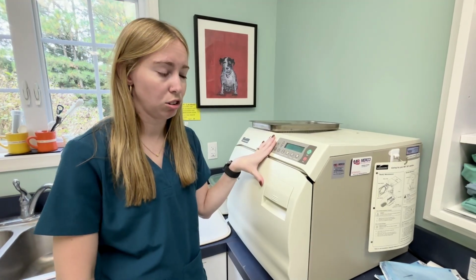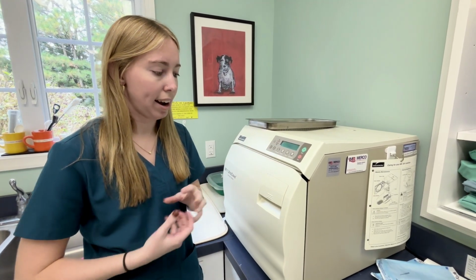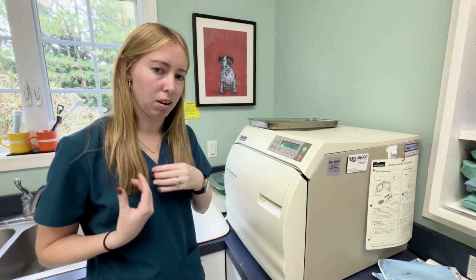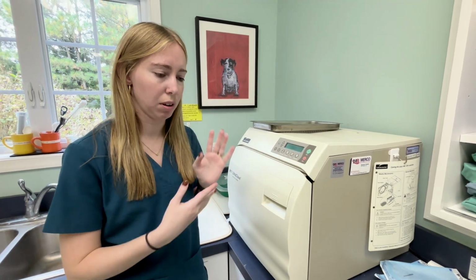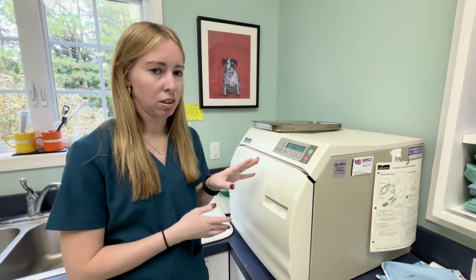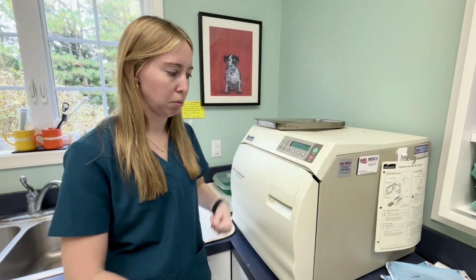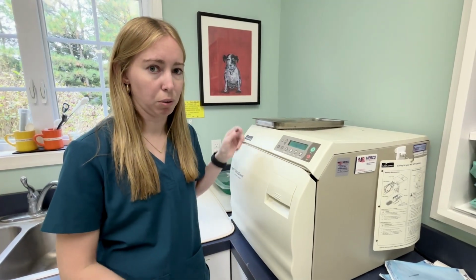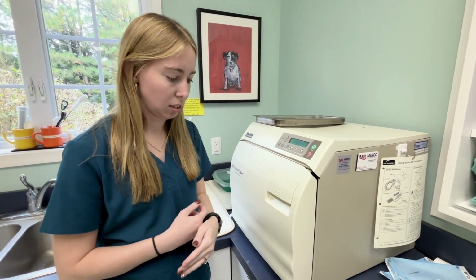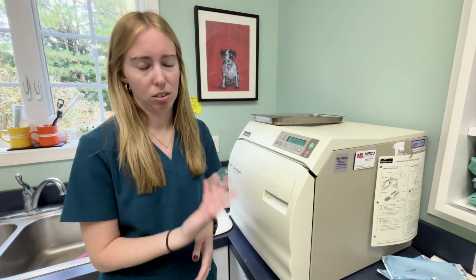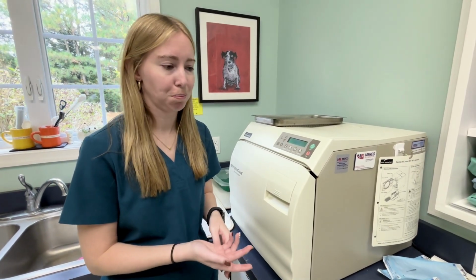And then how to properly maintain the autoclave. Once a week, we take all of the racks and all of the inner pieces out of the autoclave, and we wipe it all down with a mild soap or detergent, and make sure we empty out the distilled water line and refill it. Make sure everything's cleaned through properly so that it's sterilizing as it should.